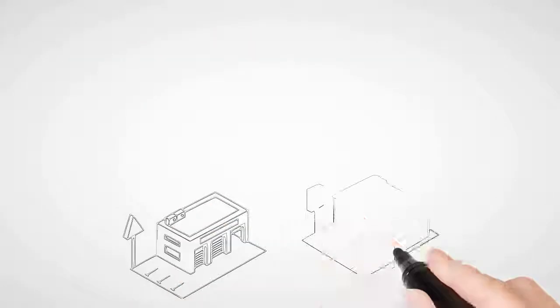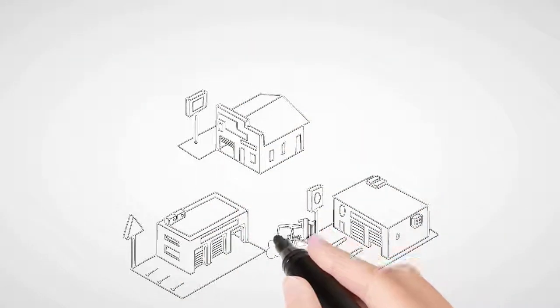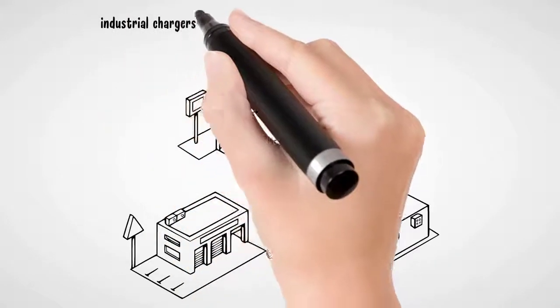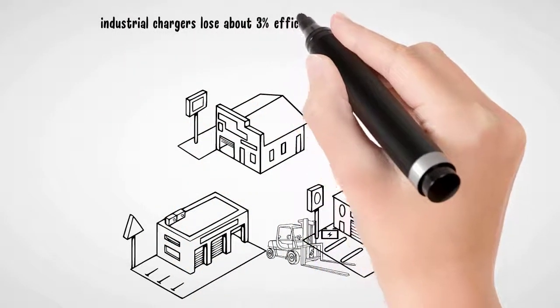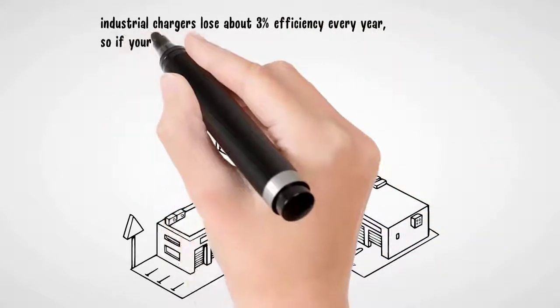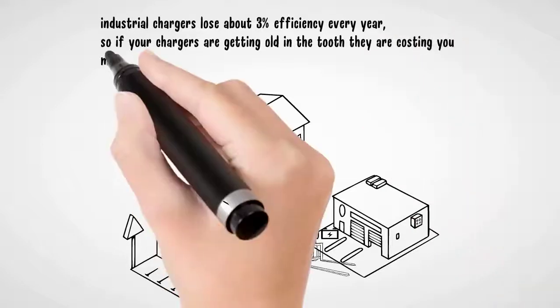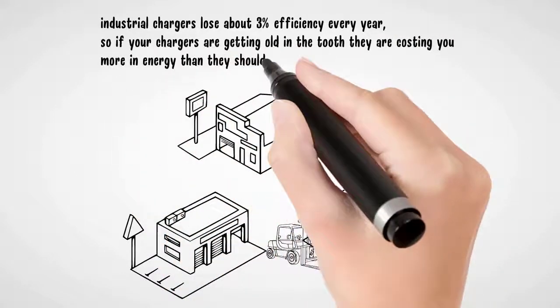Number 7: Make sure your charger is the correct voltage, amp hour range, and current output. Also, keep in mind that industrial chargers lose about 3% efficiency every year, so if your chargers are getting old in the tooth, they're costing you more in energy than they should. It might be time to replace.